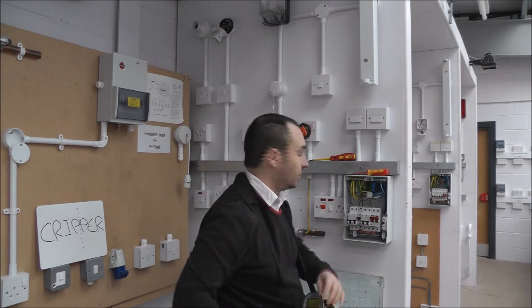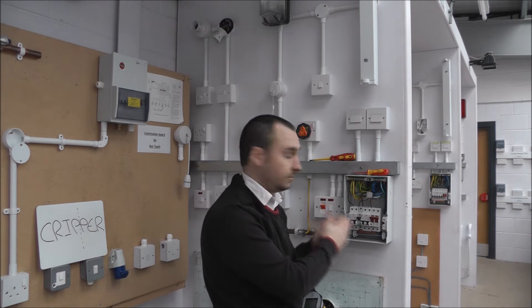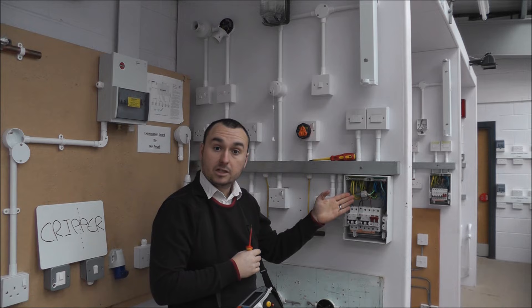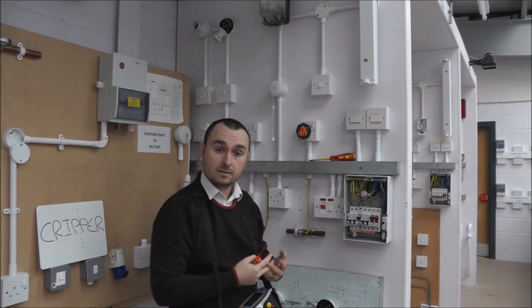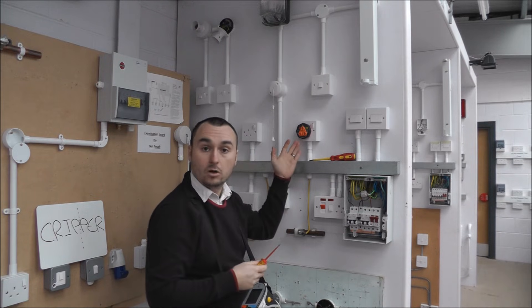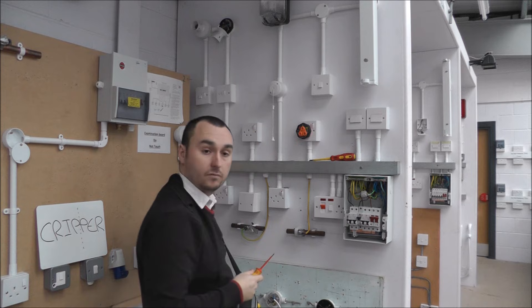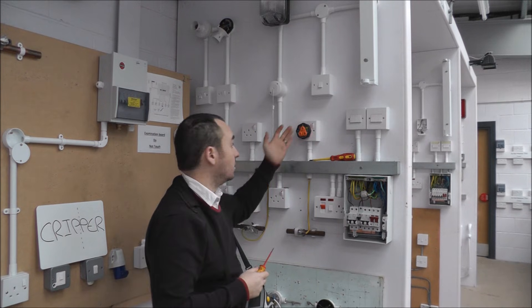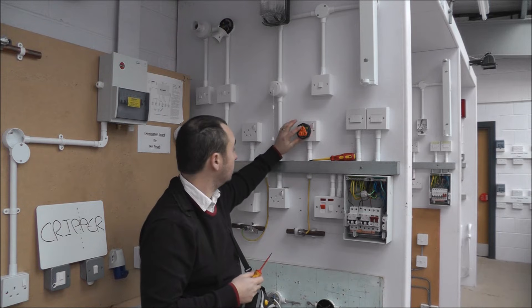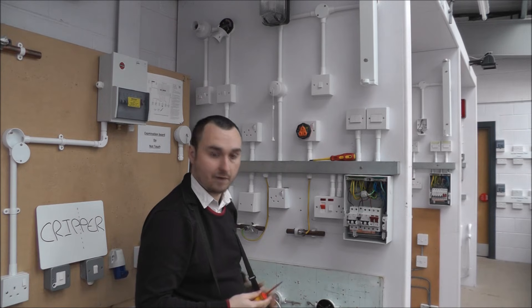Using the same figure-of-eight method, I'm now going to put my line and CPC conductors together. With the line and CPC conductors connected in the figure of eight, I can now test again at each individual socket. The reading I'm going to record on my test sheet is the highest reading from all the sockets. Testing between line and CPC helps confirm polarity, as I've just completed my R1 plus R2. My highest reading was 0.13 ohms — that is the value I will record.